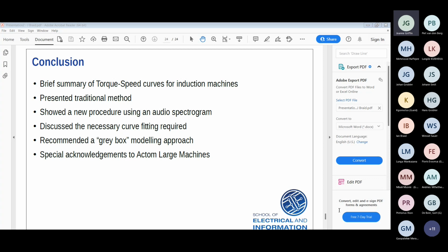We're just trying to use it as a signal which is related to the rotation. So if we could establish what's causing the vibration, or how that vibration, that harmonic, is related to the speed - you know, if it's an integer multiple - then we could use that as the speed trace. And we're looking at, in this case, the acceleration of it, so we're not looking at what the harmonic is telling us, we're just looking at whether we can measure that harmonic over time, and we'll differentiate that to work out an acceleration. So to answer your question, yes, I think a lot of the instrumentation probably is already in place and you probably could use it.